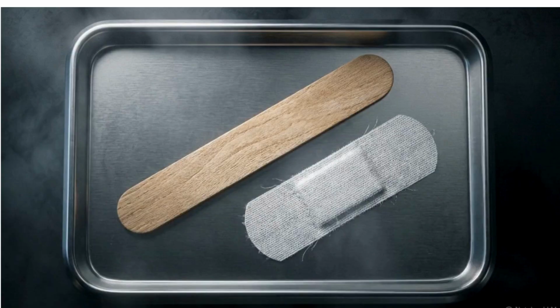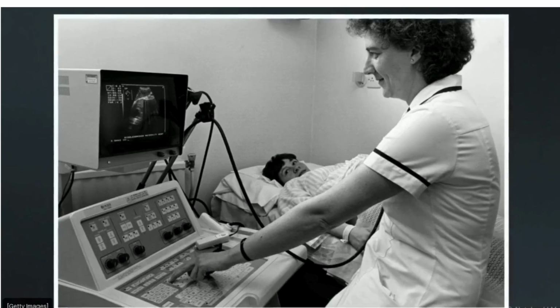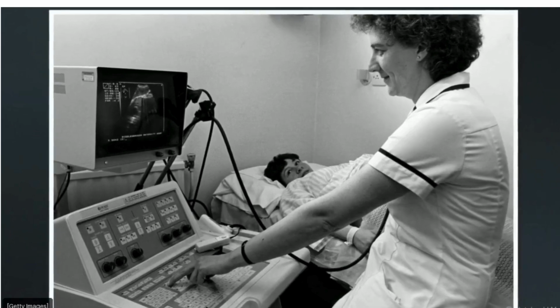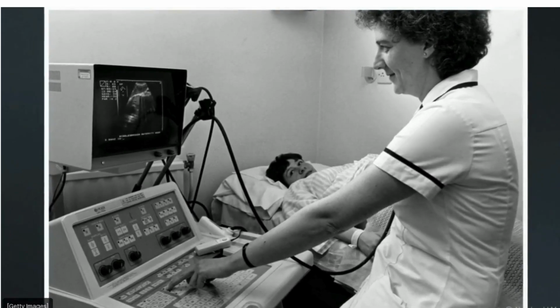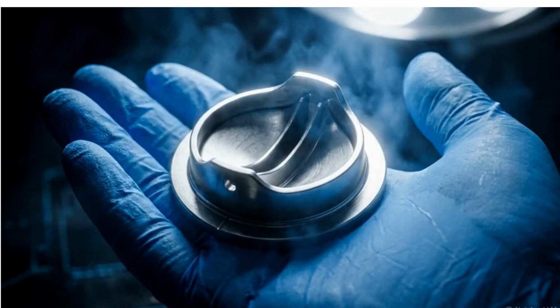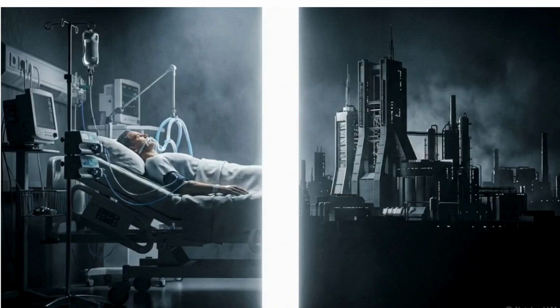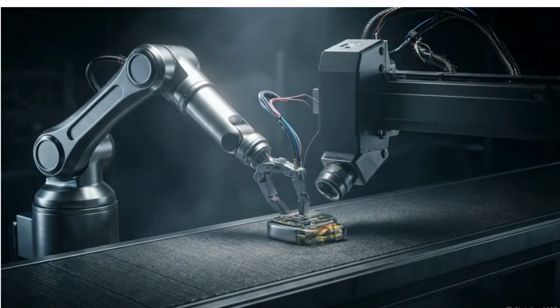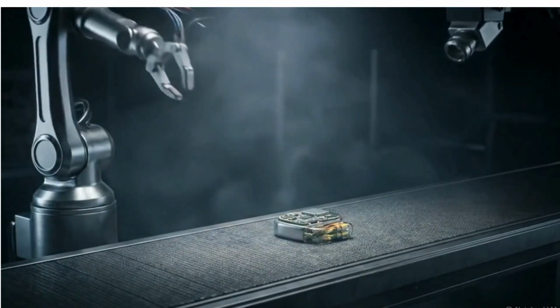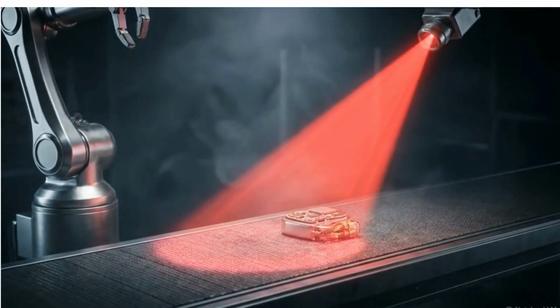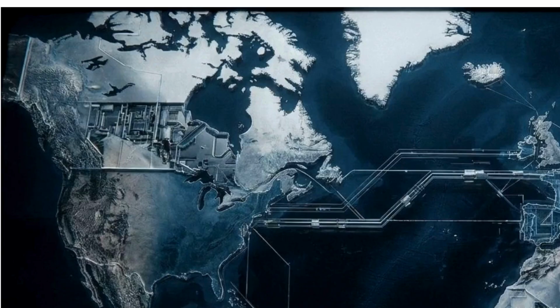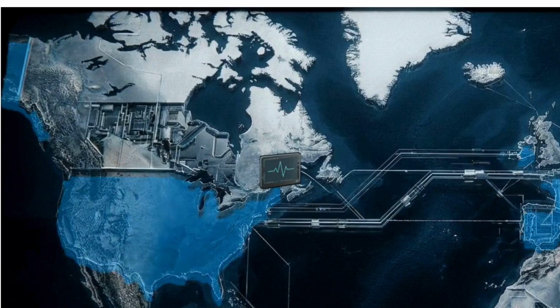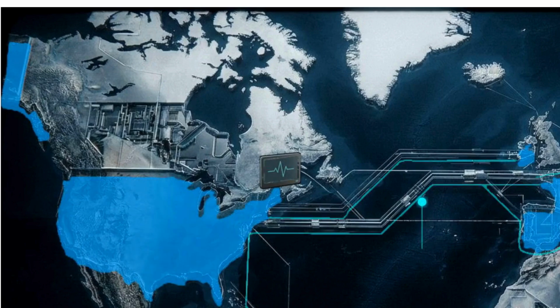A simple, non-invasive tool like a tongue depressor or a bandage sits in Class 1. Diagnostic systems like ultrasound machines carry moderate risks if they provide false readings, pushing them into Class 2. At the very top, permanent implants like pacemakers are Class 3. The stakes for the patient dictate the rules for the manufacturer. The higher that calculated physical risk goes, the tighter and more demanding the regulatory grip becomes, before market entry and long after. Once a device is classified and cleared for hospital use, it enters a global surveillance web.